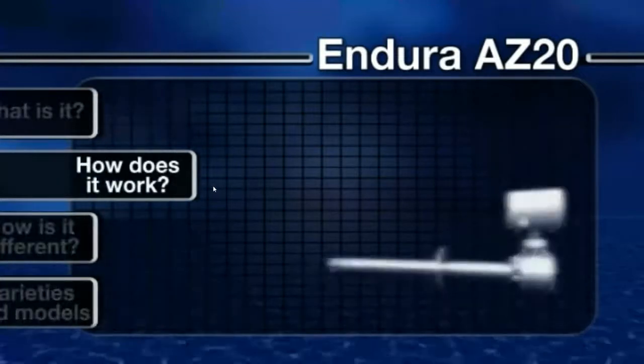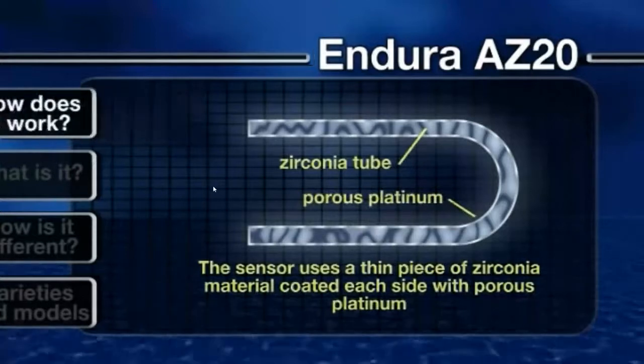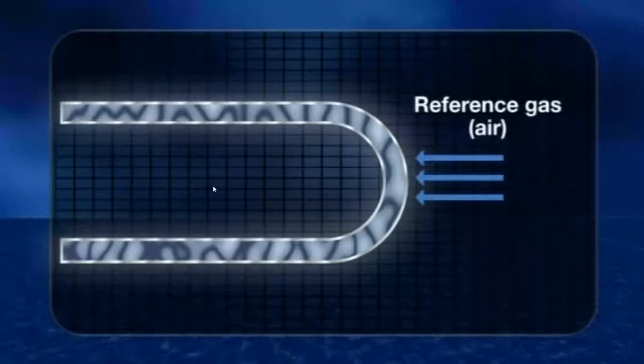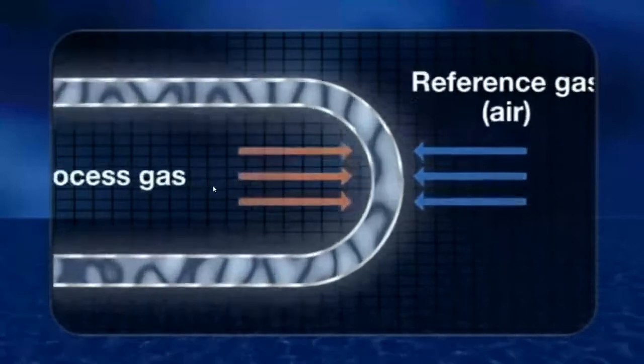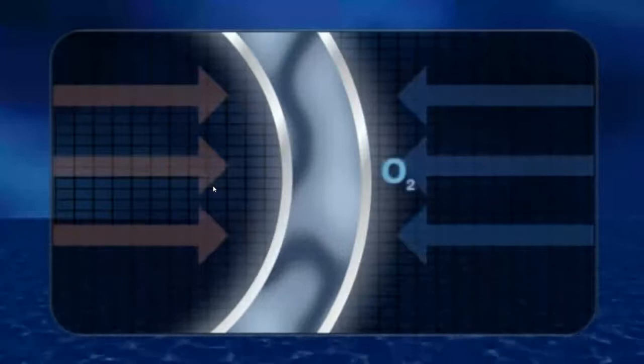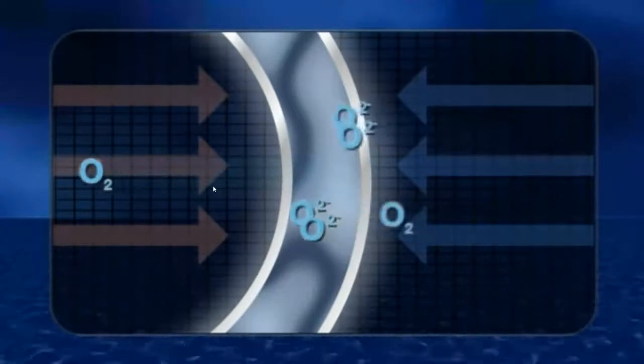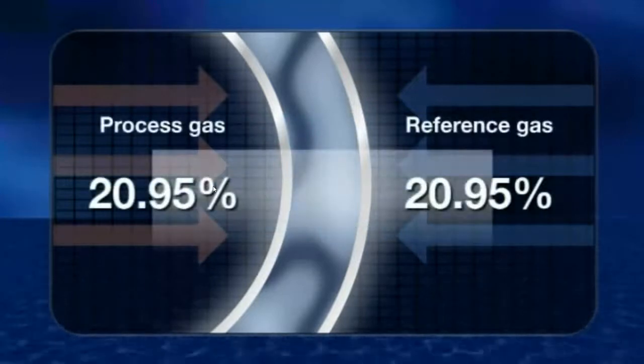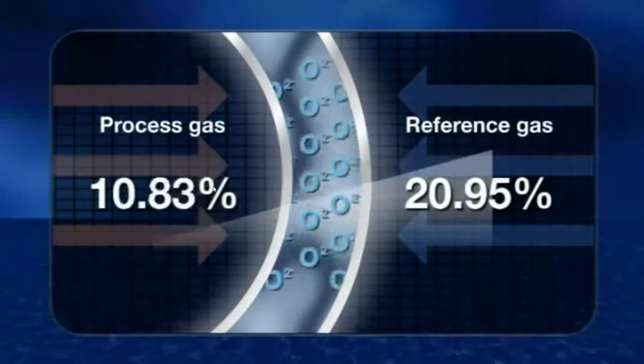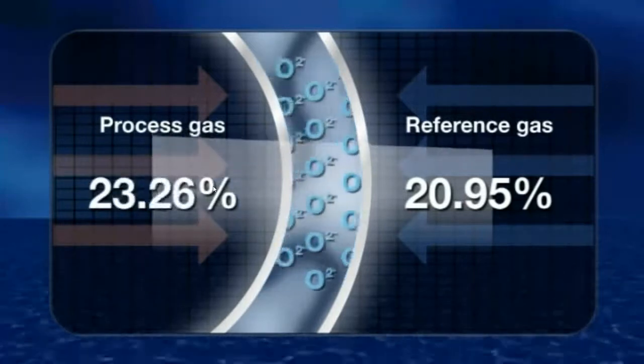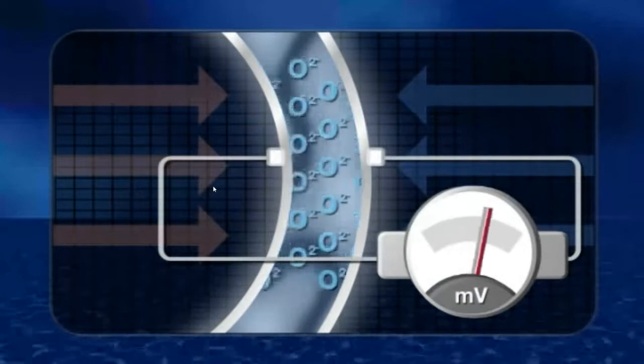How does the Endura AZ-20 work? The sensor uses a thin piece of zirconia material coated on each side with porous platinum. Air is supplied to one side as a reference gas providing a constant oxygen concentration; the process gas is presented to the opposite side. The platinum acts as a catalyst, converting molecular oxygen to oxygen ions, which migrate through the solid zirconia electrolyte. When oxygen concentration is equal on both sides, ion migration is zero. Where concentrations differ, migration increases to reestablish equilibrium, generating a potential difference used to measure oxygen concentration.